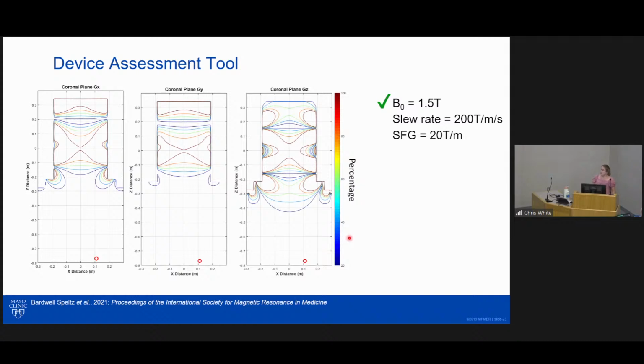That's a good question. So you could test all of these different fields. The American Standard for Testing and Materials, or something like that, gives guidelines for how to test all of these MR conditions. Say I had a new device and I wanted to test the MR conditions. They give guidelines on how to test whether the device is going to be affected by the magnetic field, the B0 field, and what strength is going to cause problems there. The spatial field gradient, heating, they give you guidelines on how to test for heating. Torque, they have lots of different guidelines. So you could follow all of those and create a phantom, put your device in, and see what measurements you get to determine safety. Because you're right, you wouldn't throw a patient in to test it. That's what the manufacturers do with their devices, follow those standards to test all of these different fields to determine safety.